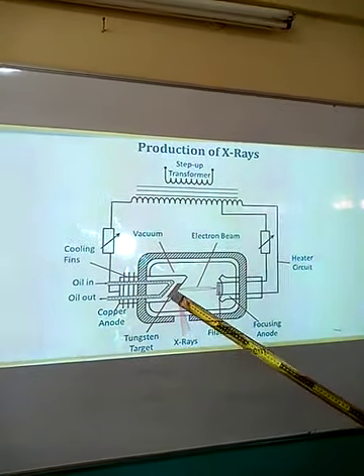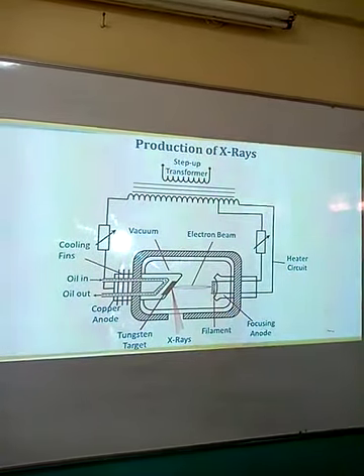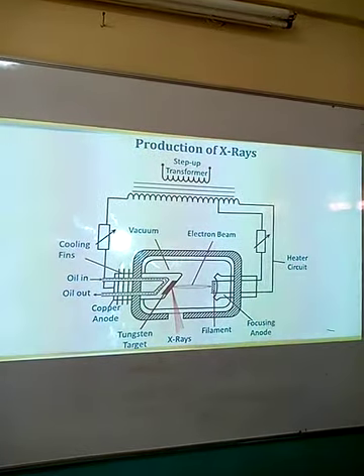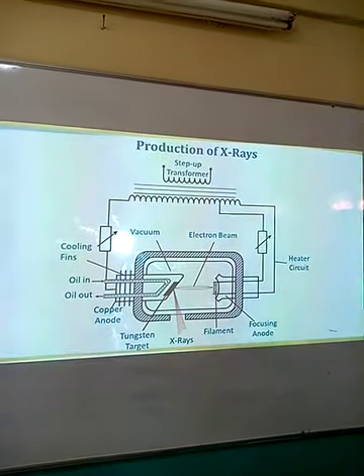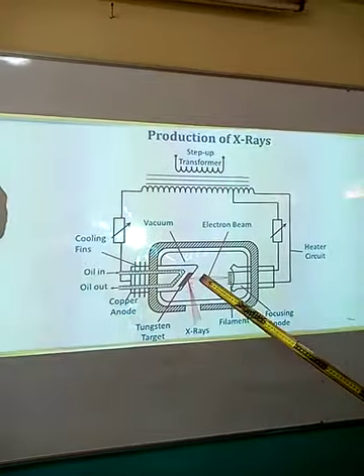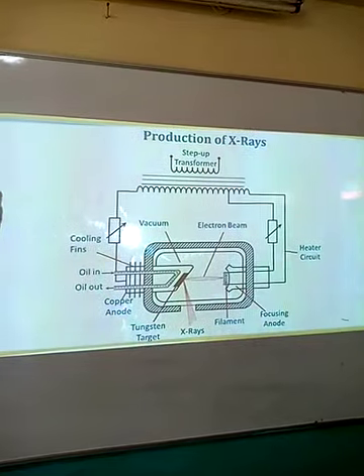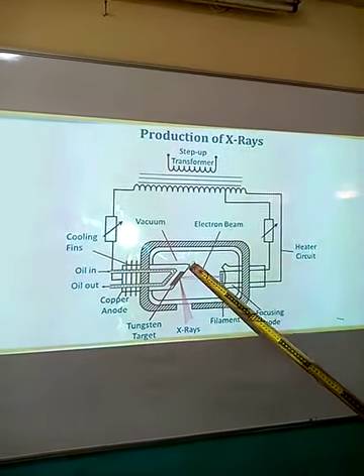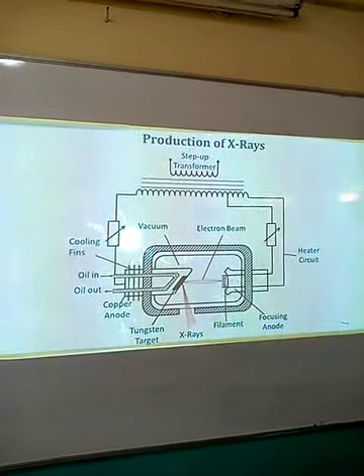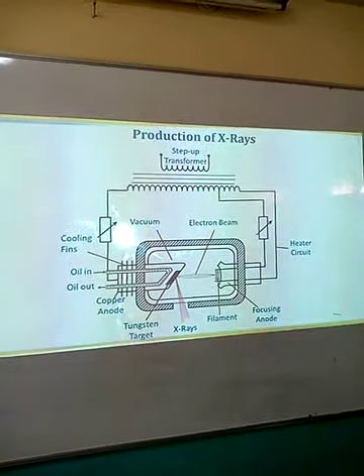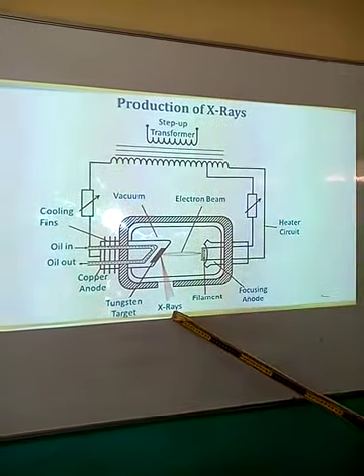The red color, as you can see, points at the electrons, which in this case we call the electron beam. It is just a massive production of electrons which are channeled to the target. And once they hit the target, 99.5% of the electrons produced are being converted into heat energy, which is being absorbed by the anode. The remaining 0.5% is the one that is used to produce the X-rays, which are channeled out of the tube through the window.